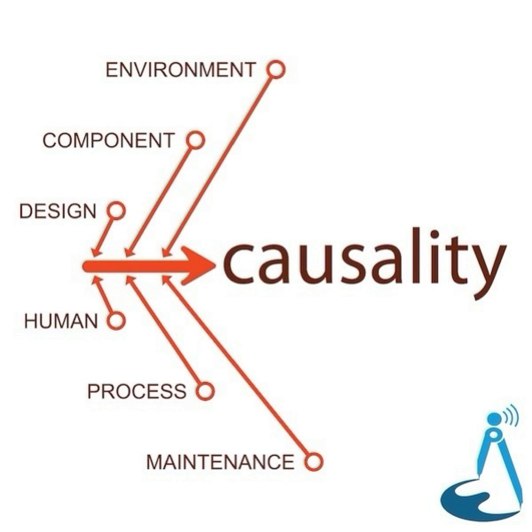If there is more relevant detail to discuss in future, if and when that happens, we may revisit this topic or we may not. Things I'd still like to know include what was the specific nature of the ACS fault? When was the ACS planned to be repaired originally? The settings on the DC battery charger outputs were biased towards station, not the Unit C4 charger. So when were they set this way and for what reason?